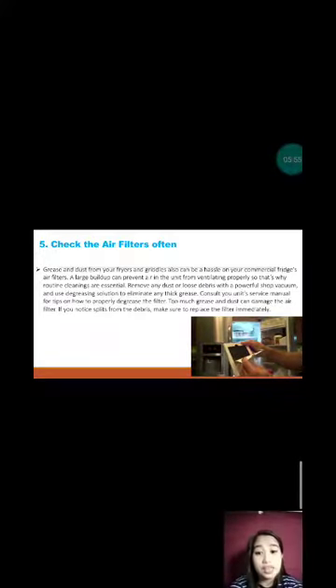And the next is we need to check the air filter often. Why often? Because grease and dust from your fryers and griddles also can be a hassle on your commercial fridges. A large buildup on air filters can prevent air in the unit from ventilating properly, so that's why routine cleaning is essential. Remove any dust or loose debris with a powerful shop vacuum and use a degreasing solution to eliminate any thick grease. So you need to consult your unit service manual for tips on how to properly degrease the filter. Too much grease and dust can damage the air filter.